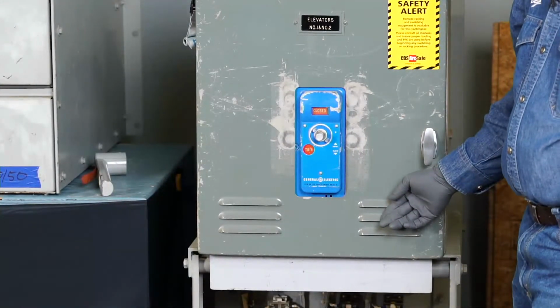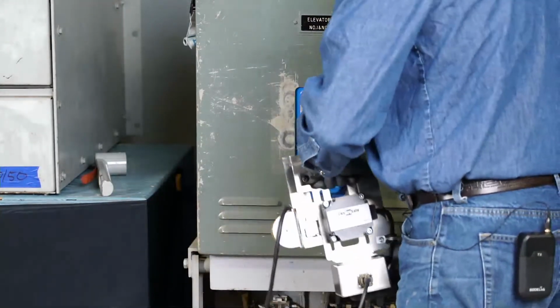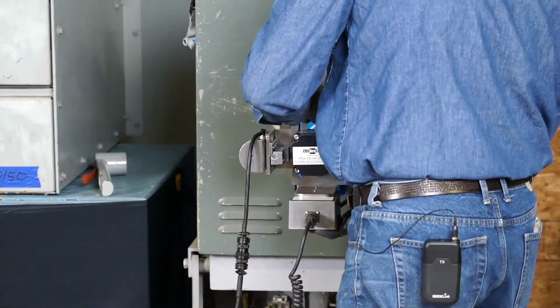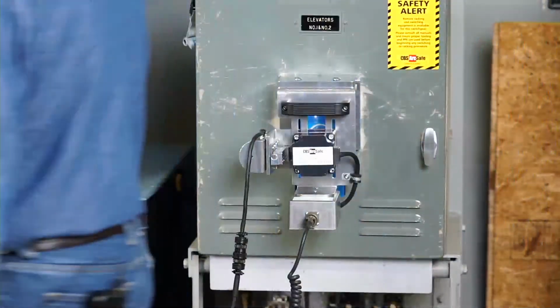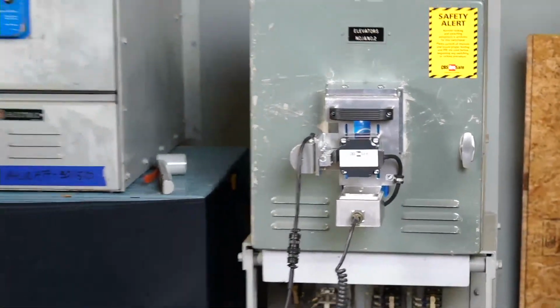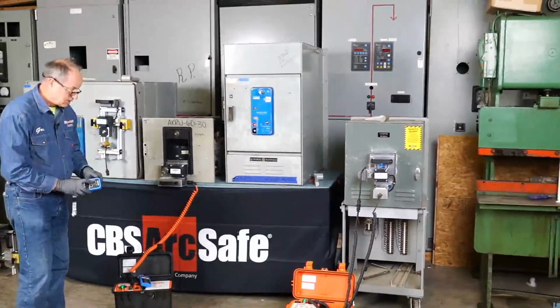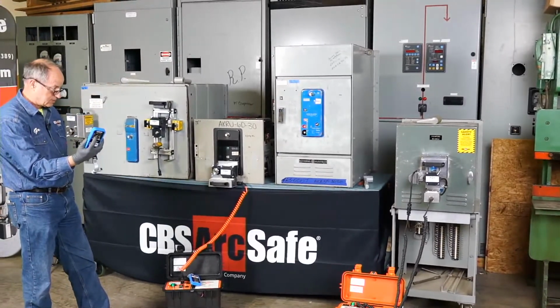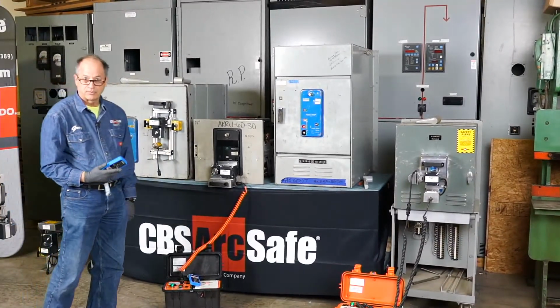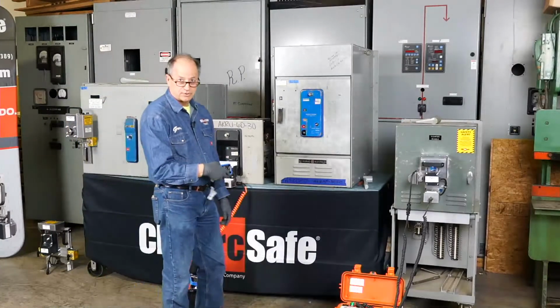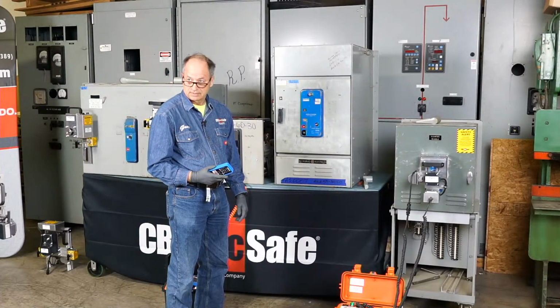If we needed to take this gear offline and trip it, what we would do is put the ArcSafe back on. Now we take our handheld remote, step outside the arc flash hazard boundary, and depress the trip button. Then you would work to rack the breaker out and then put your lockout tag out tags on it.